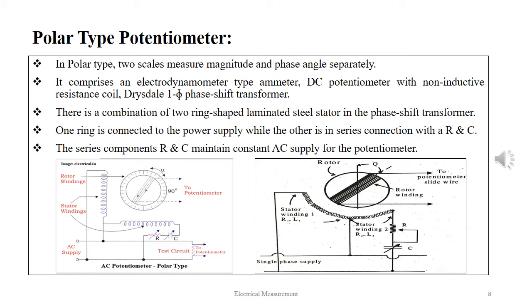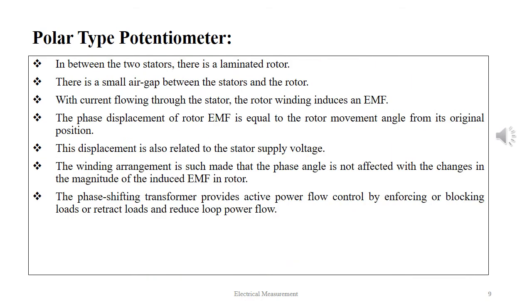There is a combination of two ring-shaped laminated steel stators in the phase shift transformer as shown below. One ring is connected to the power supply while the other ring is in series connection with the R and C component. The series components R and C maintain constant AC supply for the potentiometer. In between the two stators, there is a laminated rotor. There is a small air gap between the stators and the rotor.